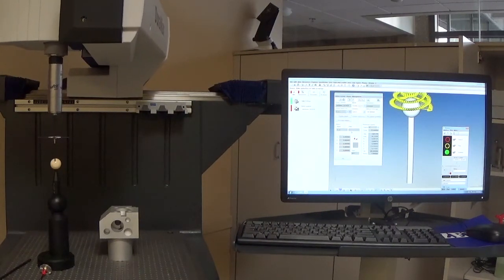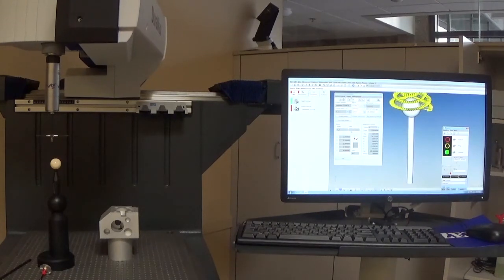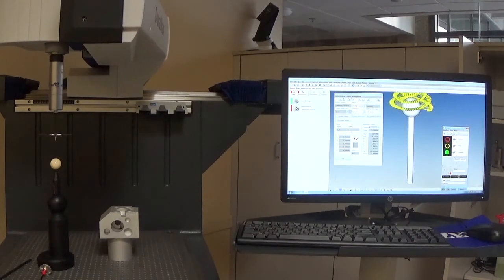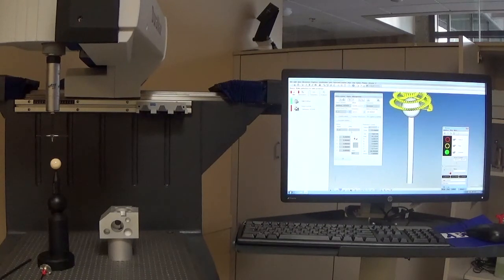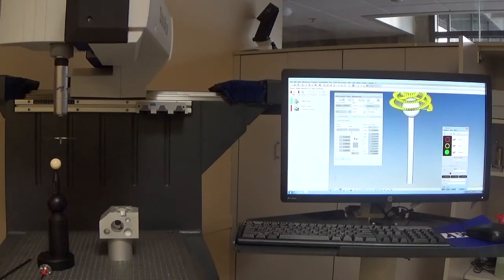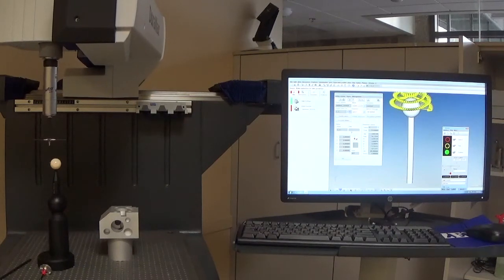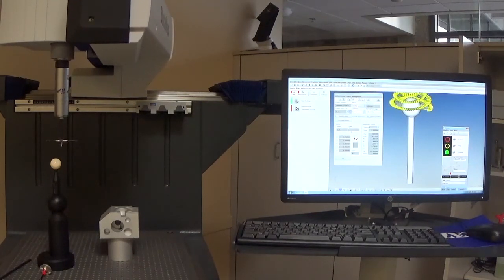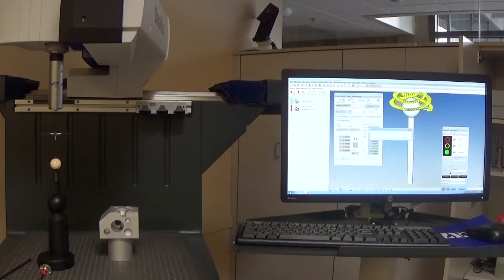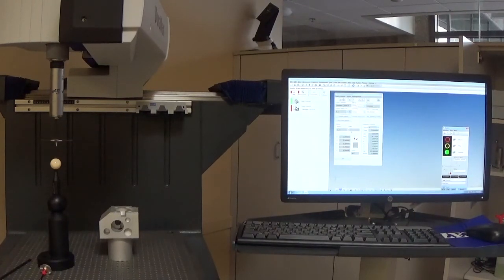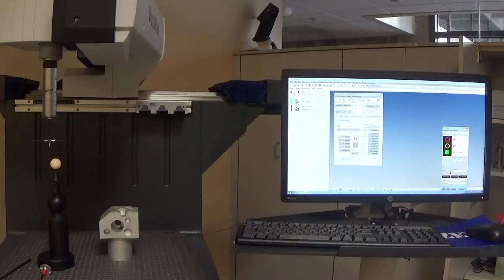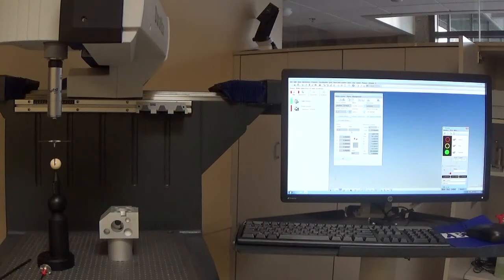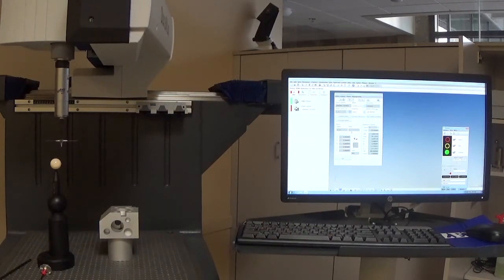So when Calypso does a stylus qualification, when it scans around the qualification sphere, it's creating a deflection matrix. Because Calypso and Zeiss like scanning, they need to know how that probe is going to react as it touches different surfaces in different directions. So it creates that deflection matrix so it can comp the probe correctly depending on how it's measuring. So it needs to go through all of these sequences to create all of that information so that it can measure accurately. So the last step that it's doing now is finding that sphere, measuring and calculating the diameter of the stylus ball. So this is the end of the routine for the qualification of Stylus 1 of my stylus system.